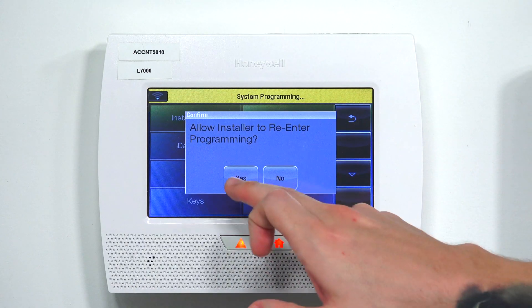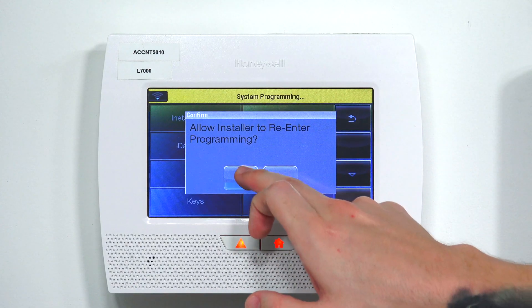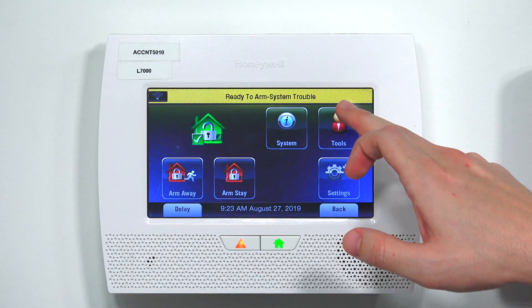One important thing when you guys are exiting programming: there's going to be a screen that says, do you want to allow the installer to re-enter programming? It's always important that you say yes. If you say no, when you try to go back into programming it's not going to let you — it's going to lock you out. Then you have to do a backdoor programming method, redo the process, and say yes so the panel refreshes.